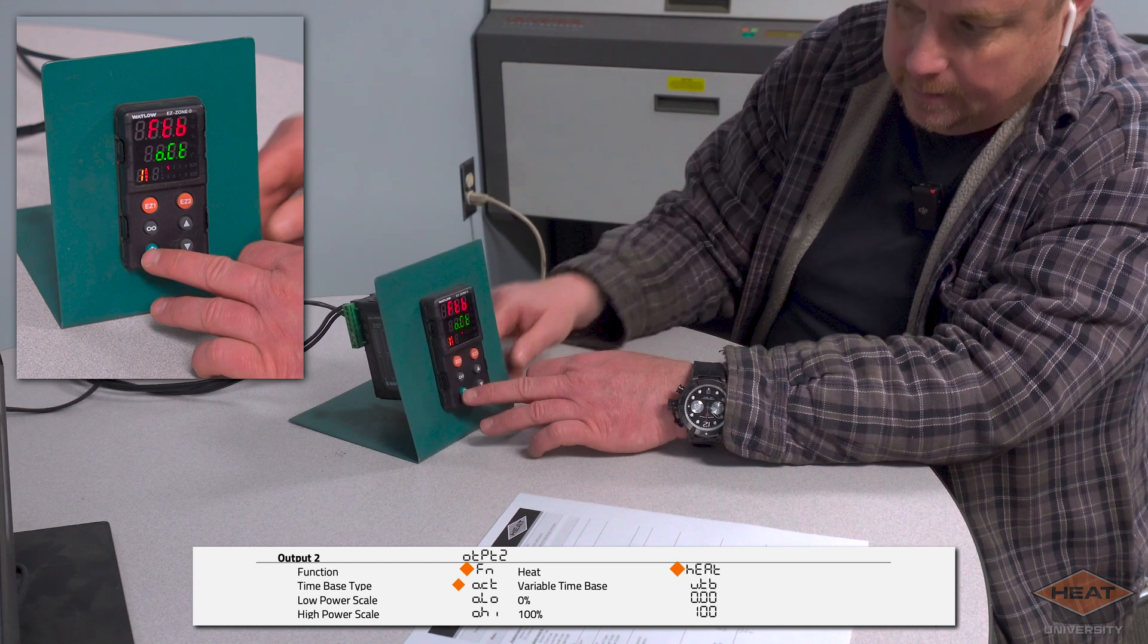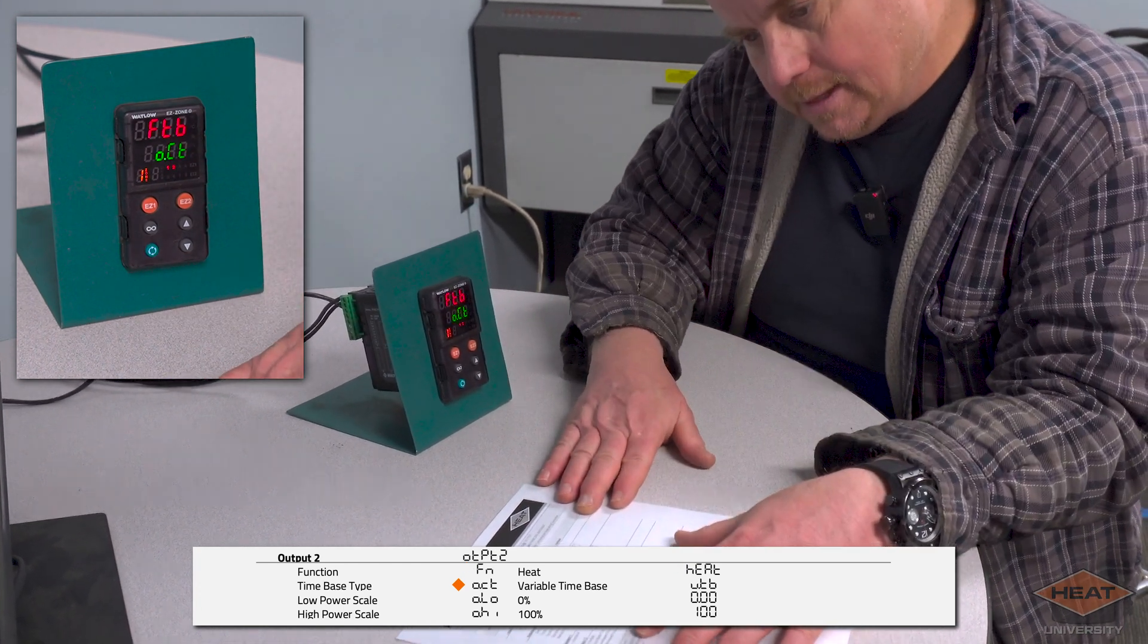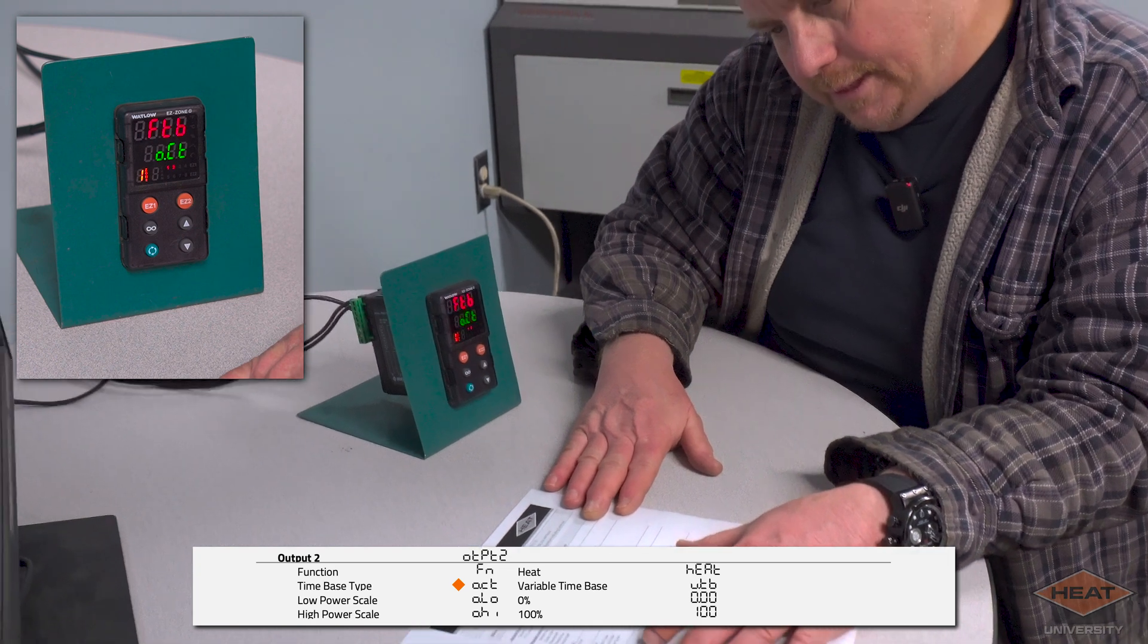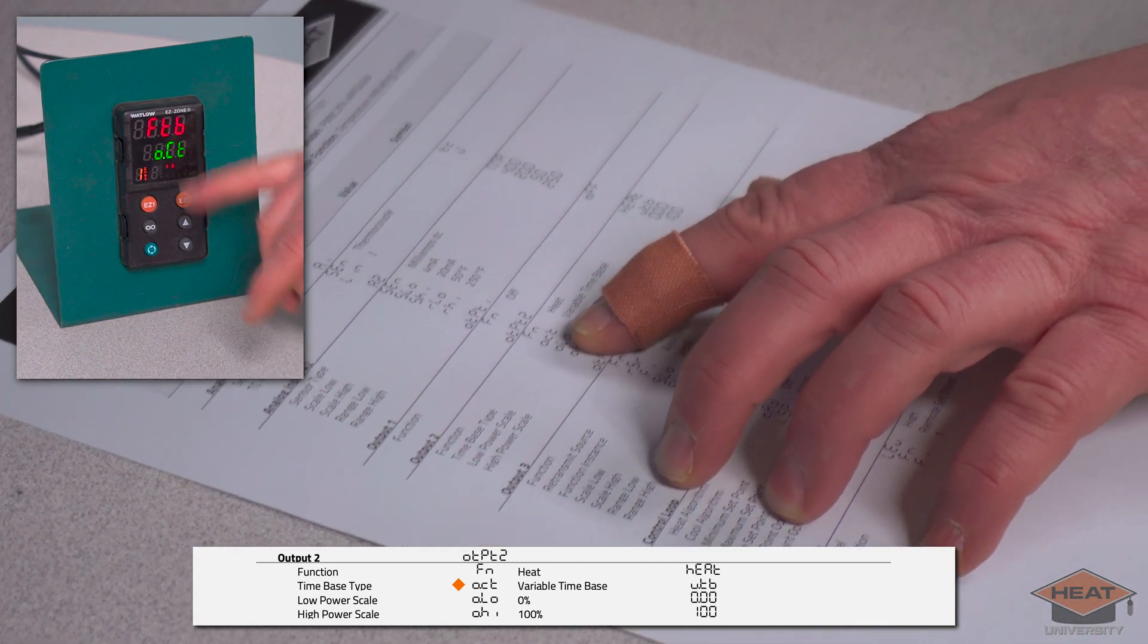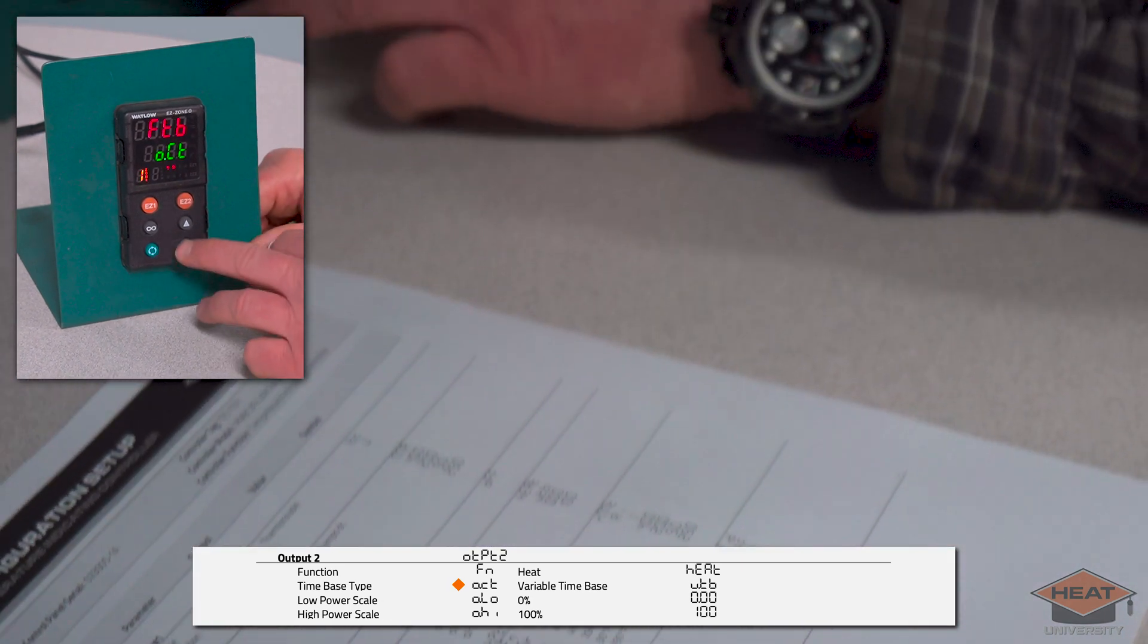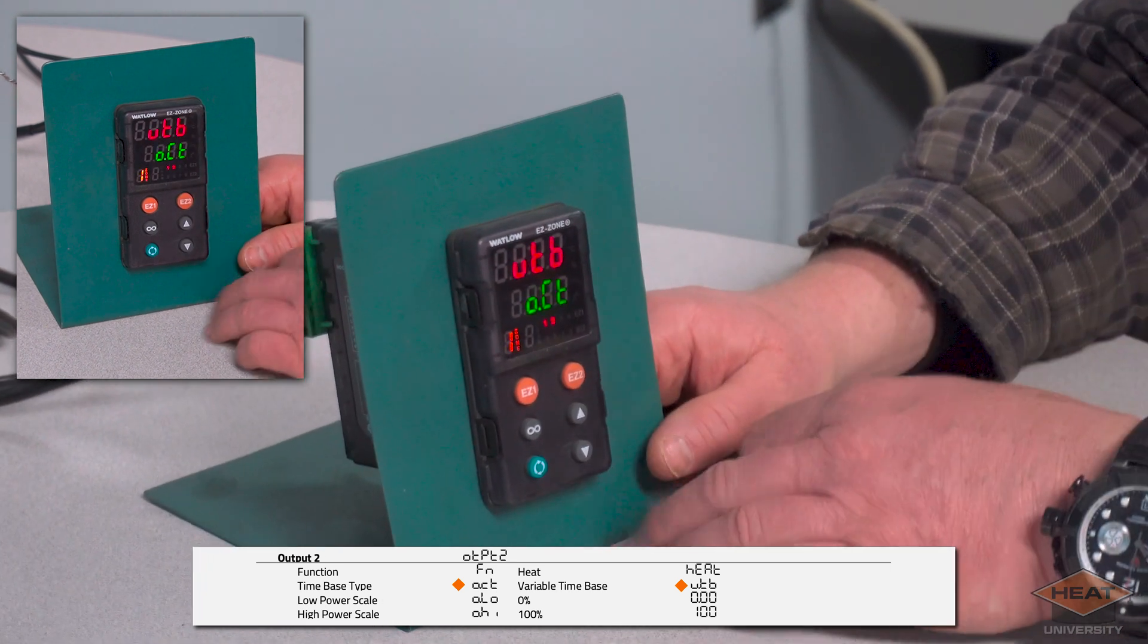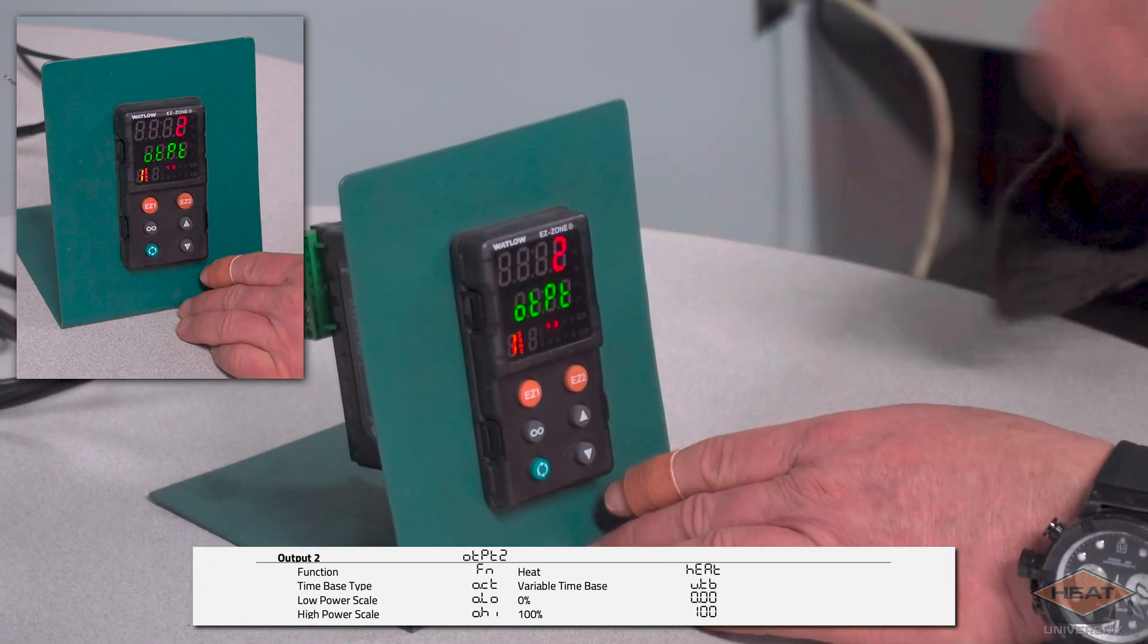Then I'm going to hit the cycle button. It comes up alarm, so we're going to cycle down through off, cool, heat. We're going to select heat. Then this right here, our output time base—I don't know if you can see this—it's our time base type OCT, and then we want variable time base.